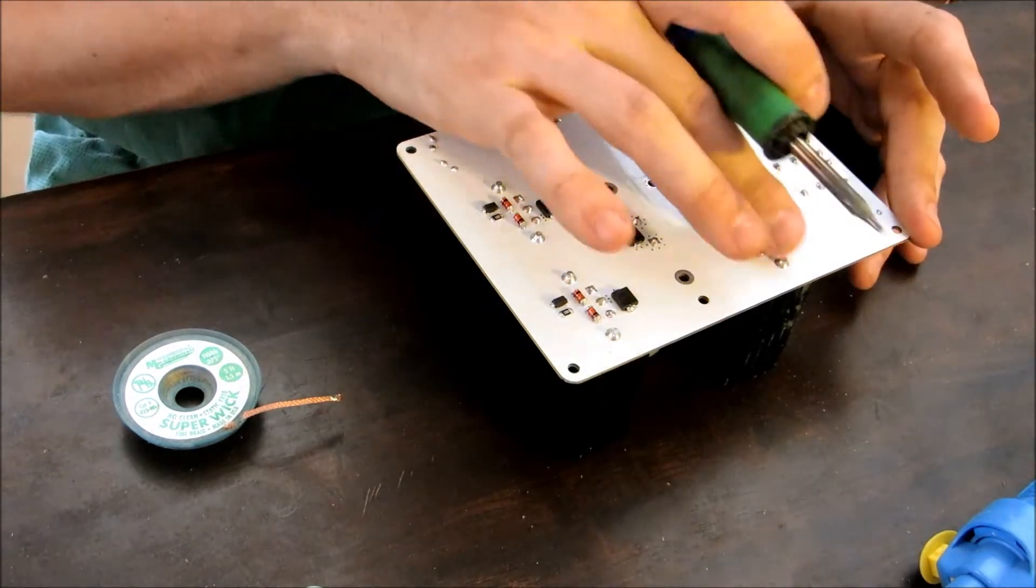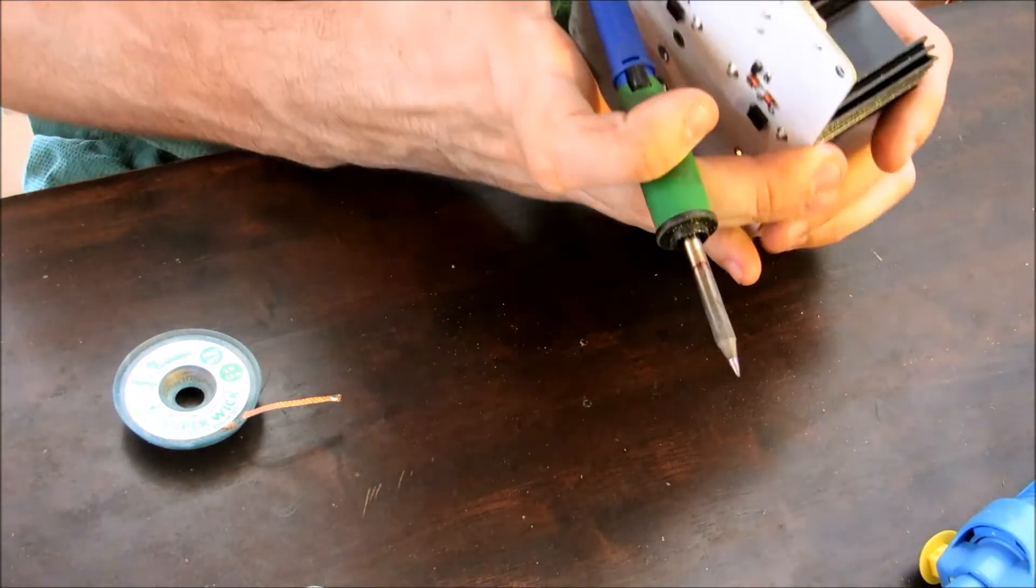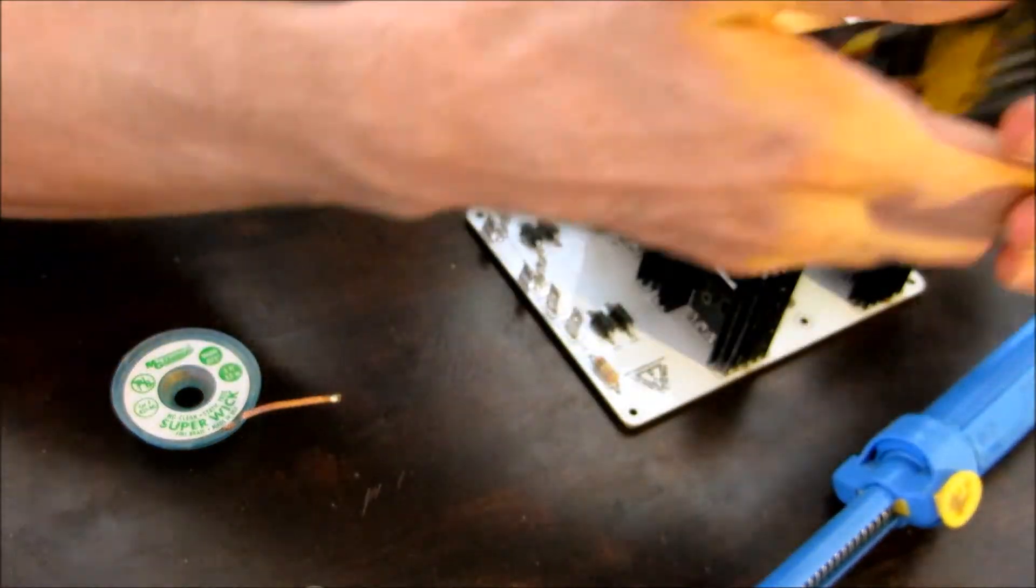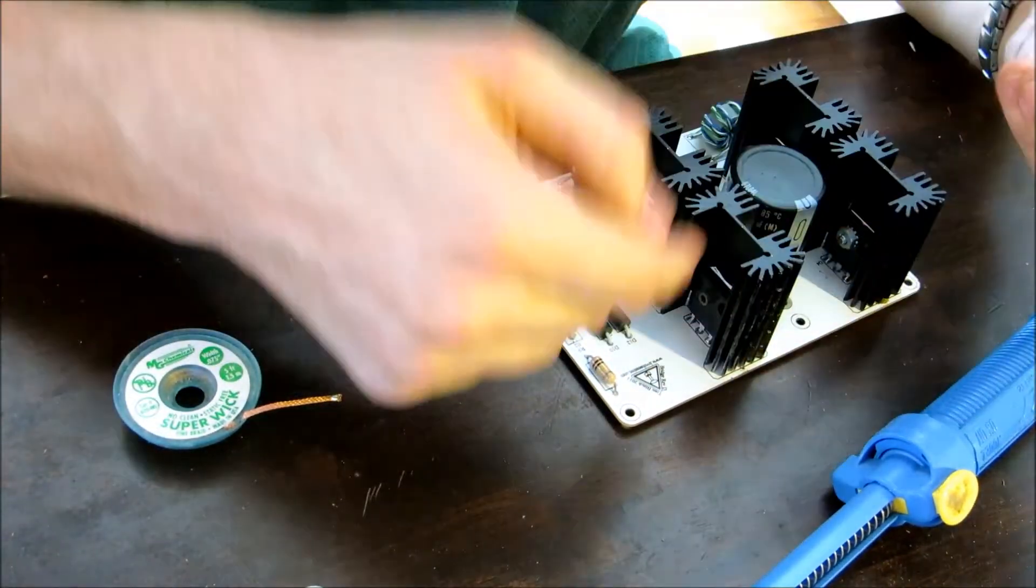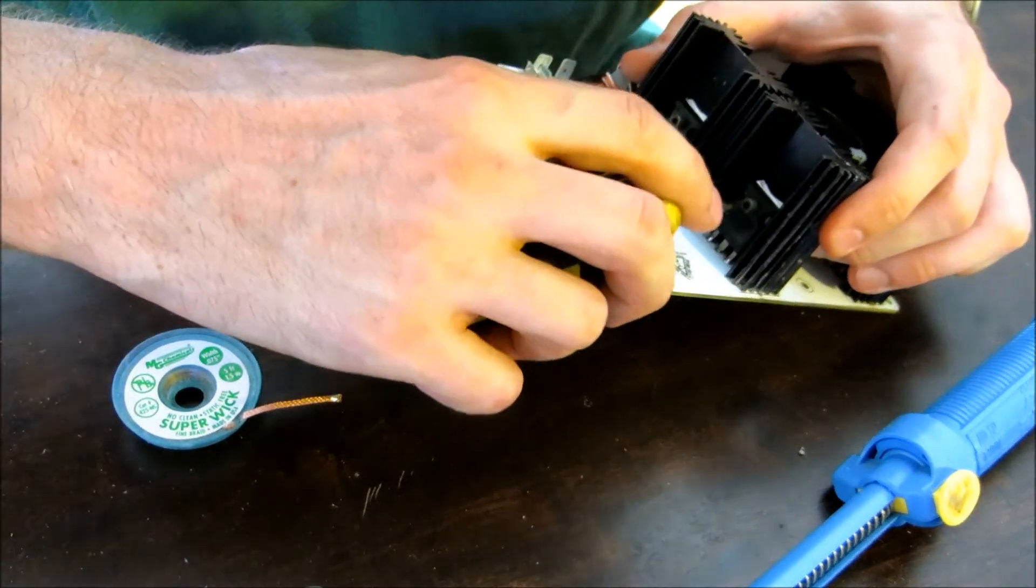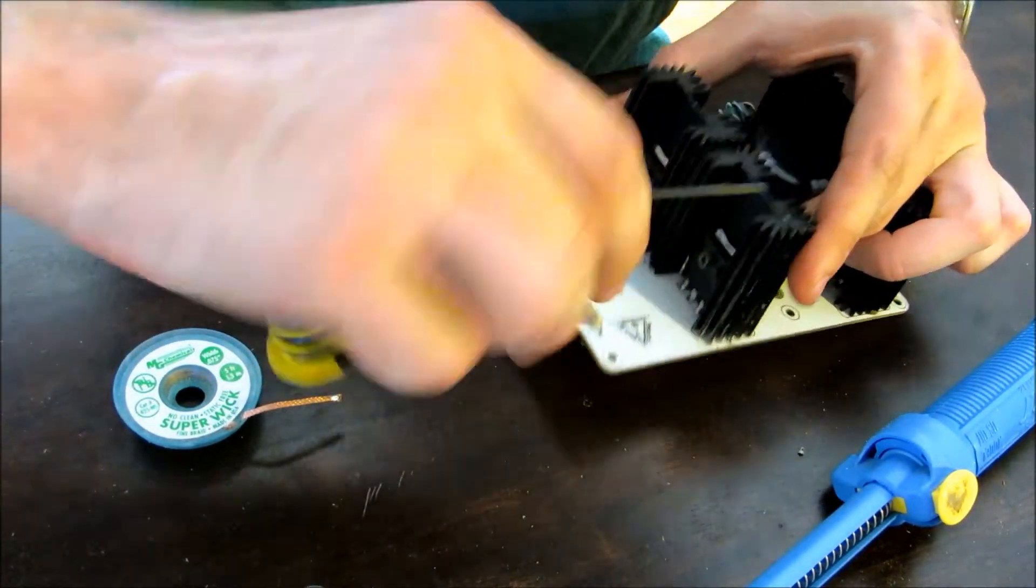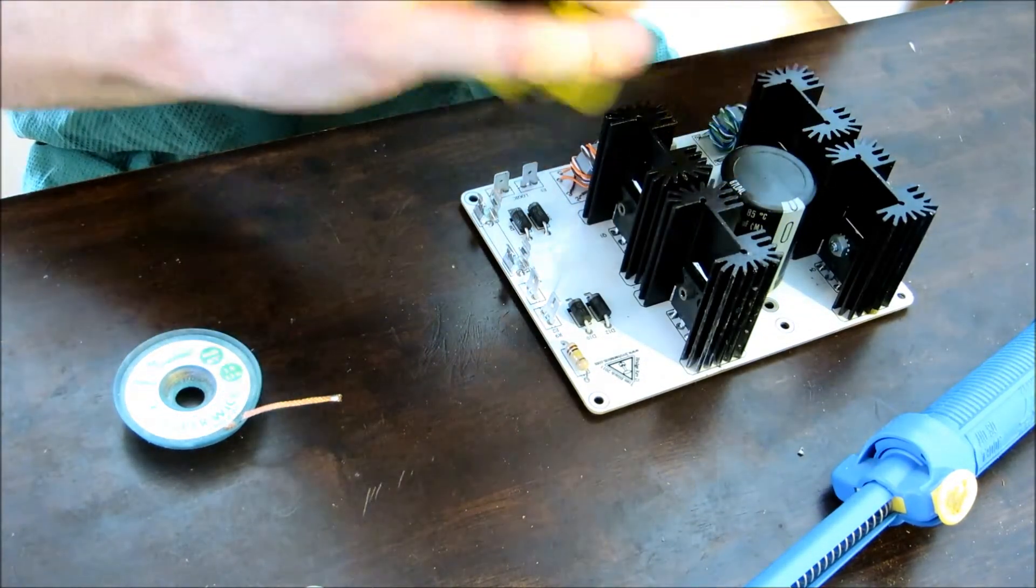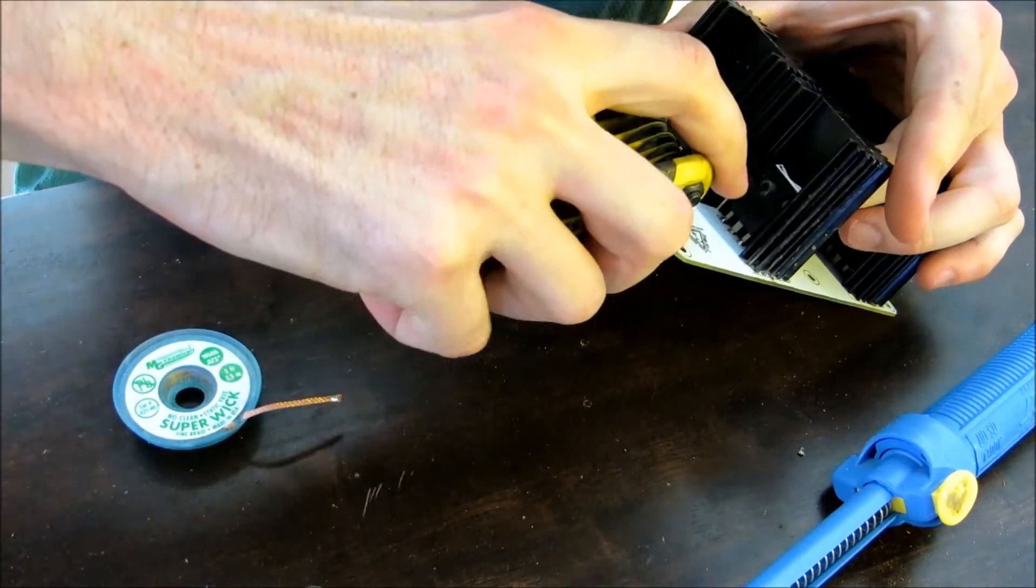All right, so now that you know it's this side, the first thing you want to do, which is going to make this about 10 times easier than it would be, is you want to remove the screws and push the IGBTs off the heat sink, because that's what's going to be, or your heat's going to be going into the heat sink, and it's going to be a lot harder.